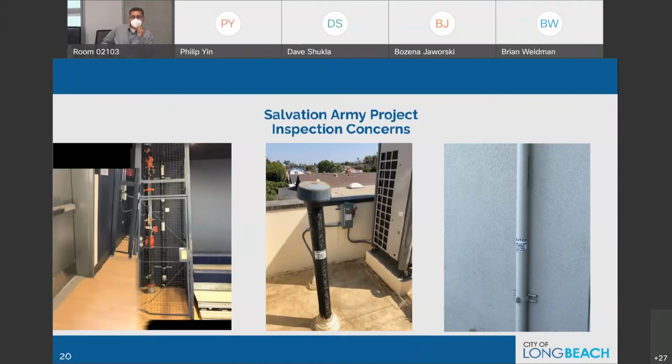Okay, now if any pipe of a venting system, a methane venting system, is run, it must be in an approved location, and the pipe vent must be identified with a sign reading no electrical equipment or sparks within 10 feet, and cautioning there's methane, or maybe methane, in this pipe. And from there, I'd like to direct your attention to the picture in the middle.